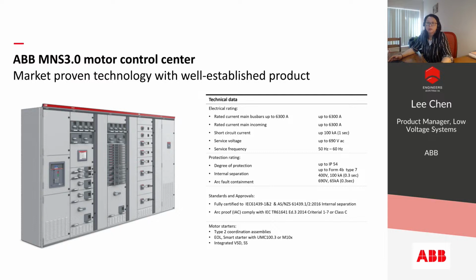So ABB low voltage MCC is based on MNS3 switchgear. MNS3 is a front access indoor switchgear which is rated up to 6,300 amps, 100 kA. It is a type-tested assembly to IEC 61439 and arc-proof tested to IEC 61641 criteria 1 to 7 to ensure a high level of safety and reliability among our market peers.